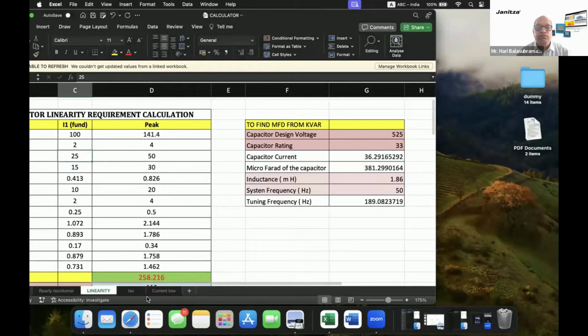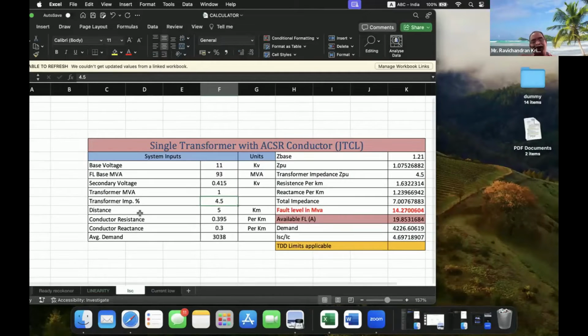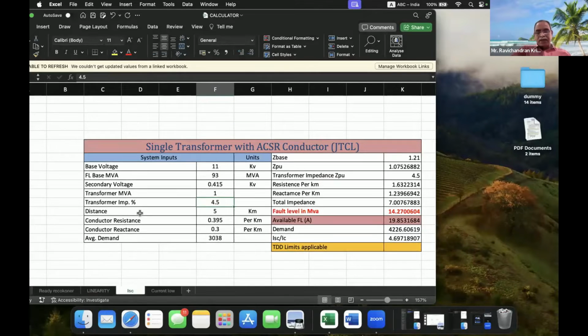Okay. For the resonance frequency, I suggest finding the short circuit level, ISC, available from the source. Generally, it is calculated based on the transformer installed capacity in MVA. But most probably, whenever I am doing the audit, that is misleading, because the source impedance is an important key factor to decide. And based on that only, IEEE 519 is also giving the recommendations. Now it becomes a standard. And as we discussed in the last meeting about 2-4, it is based on that.